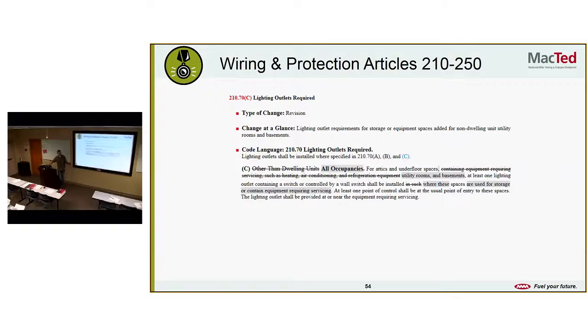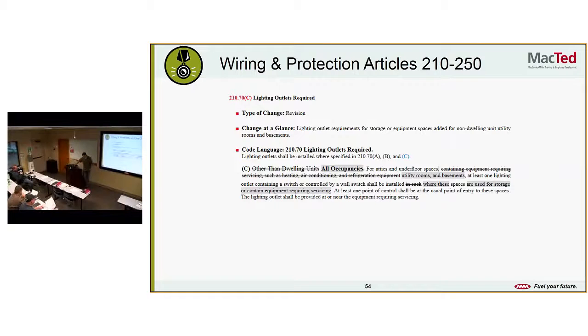There's been a revision to the lighting outlets that are required for all occupancies. So this is for everything. For attics and underfloor spaces, they've taken out containing equipment requiring service such as heating, air conditioning, or refrigeration equipment. And they've put in utility rooms and basements, at least one lighting outlet containing a switch or controlled by a wall switch shall be installed where these spaces are used for storage or contain equipment requiring services. So here we're thinking like maybe an attic with a furnace in it, basements where you're going to store things, or crawl spaces. So people aren't putting stuff in storage areas without any lighting. And with a way to control that lighting.